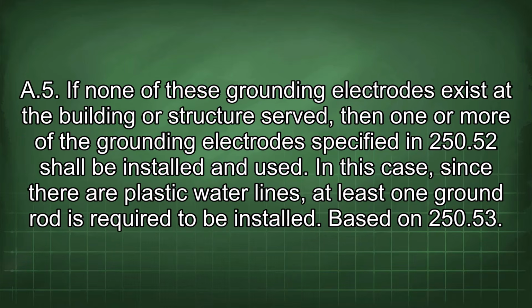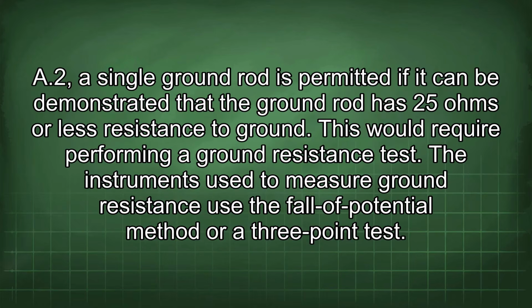250.52(A)(5). If none of these grounding electrodes exist at the building or structure served, then one or more of the grounding electrodes specified in 250.52 shall be installed and used. In this case, since there are plastic water lines, at least one ground rod is required to be installed. Based on 250.53(A)(2), a single ground rod is permitted if it can be demonstrated that the ground rod has 25 ohms or less resistance to ground. This would require performing a ground resistance test.